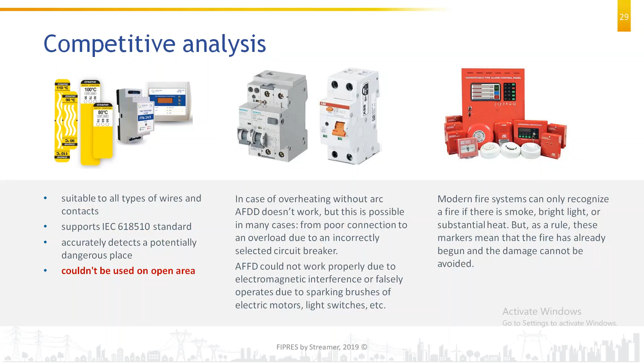Then the normal thing we do for monitoring overheating of the terminals and different points and areas is the thermography camera. We will compare our solution with a thermography camera. FIPRES works round the clock. Thermography works only at the time of inspection. FIPRES allows checking equipment in locked explosion proof enclosures and high voltage panels. However, the thermography camera doesn't allow checking equipment in locked explosion proof areas.